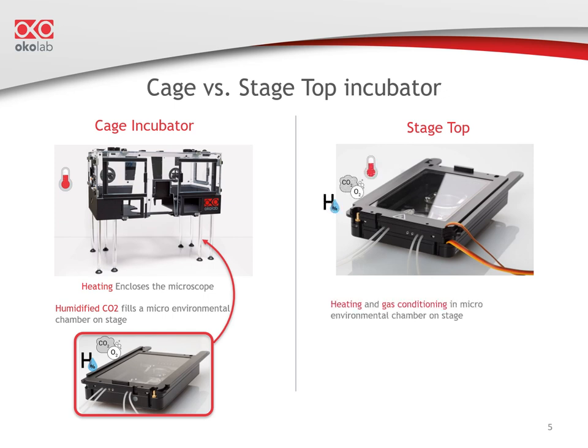In a stage top system, both heating and gas conditioning are provided by the microenvironmental chamber. There are some electrical contacts, the lid is heated, the glass on the lid is coated with indium tin oxide also providing heating, and the sides of the chamber are heated as well.